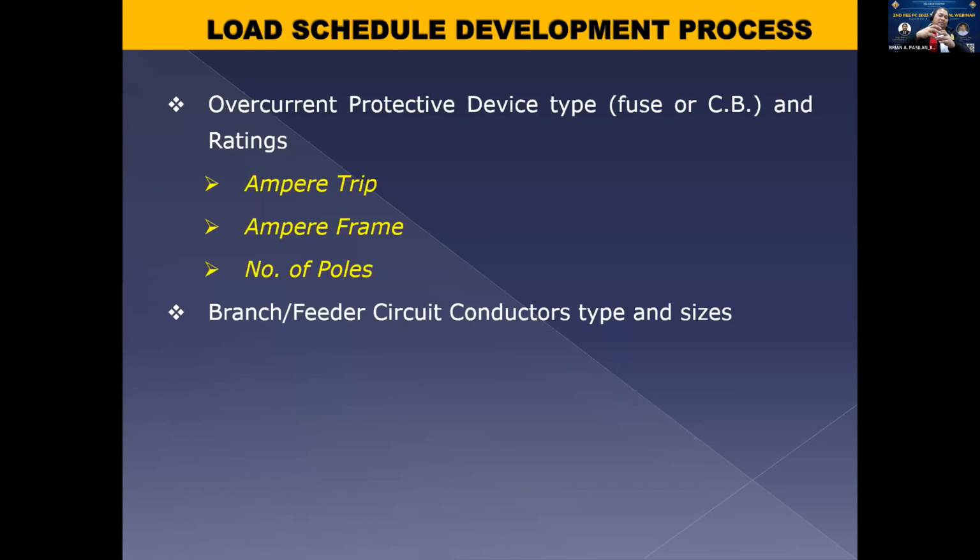Meaning to say, kung gusto mong mag-upgrade from 20 amperes to 50 amperes, hindi mo na problemahin kung mag-fit in ba yung circuit breaker mo kasi they are on the same ampere frame. So convenient yan sa atin, sa mga installers, no? Na kung gusto mong palakihin kasi may additional loads ka, hindi mo na kailangang isipin kung paano natin i-fit in yung circuit breaker, mag-retrofit ba tayo sa panel board, hindi na, basta within lang sa same ampere frame yung breakers natin, no? So yan yung kahalagahan ng ampere frame, no?